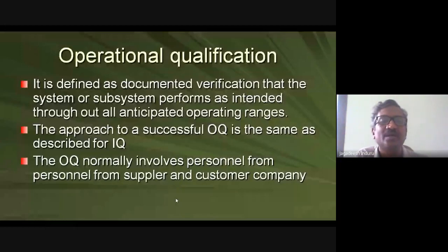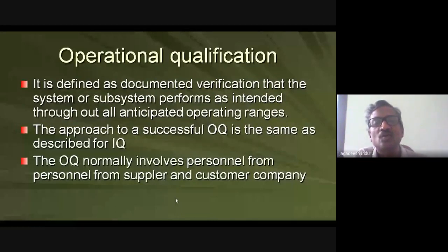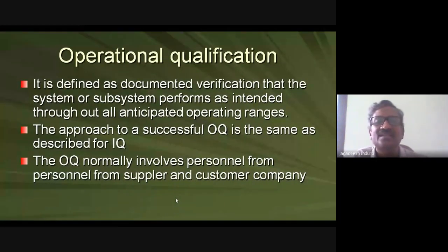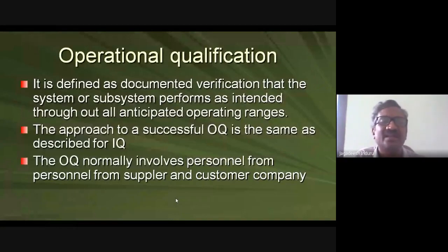If you intend to heat at 250°C but the dryer only reaches 200°C maximum, or goes beyond 300–400°C without control, the operational qualification fails. Similarly, if a vacuum pump intended to reach 0.1 mm Hg cannot achieve it, that part of the system is rejected. Even though installed, the equipment cannot be used in the factory unless the entire lower and upper operating limits — such as the compression machine's RPM range — are verified.